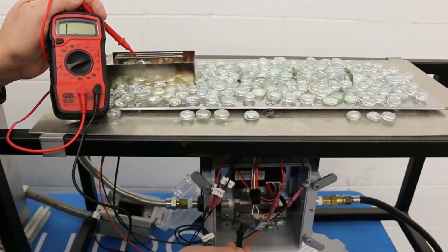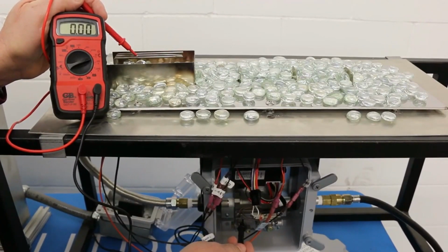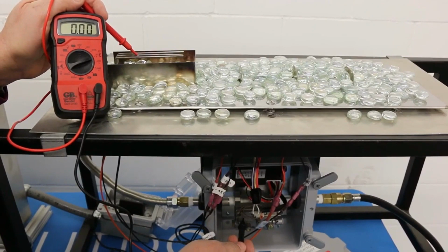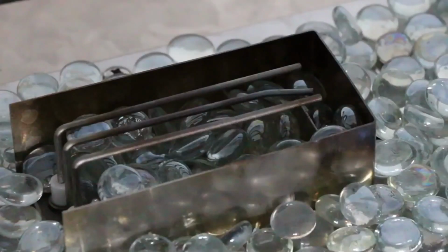Although unlikely, you should also check your ground. Do this by checking continuity between the center probe of the electrode and the metal body of the valve. If no continuity, order a new ground wire. Now let's troubleshoot the scenario where you do hear the spark but don't see the spark or the spark is very weak. When you turn on the unit, you should now hear and see the spark between the igniter rod and the center grounding wire. This may be difficult to see in bright sunlight.